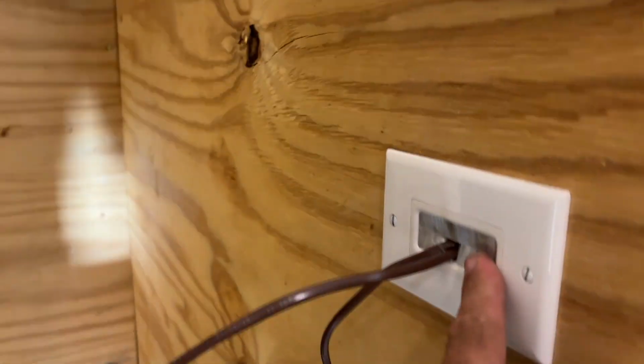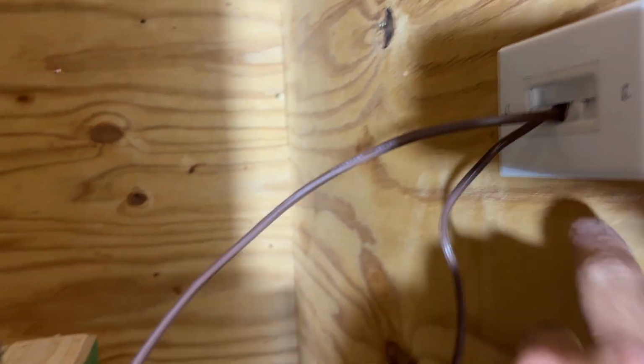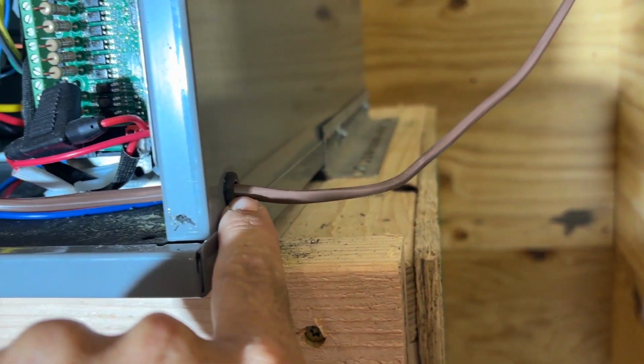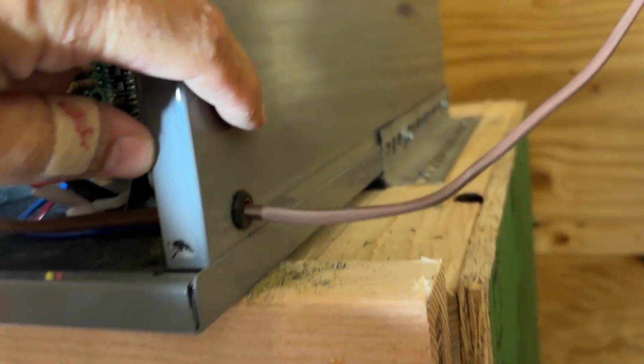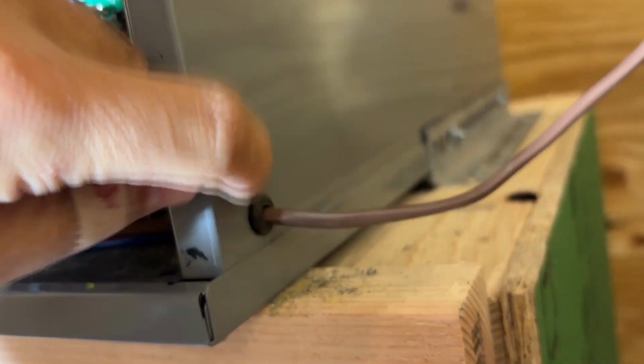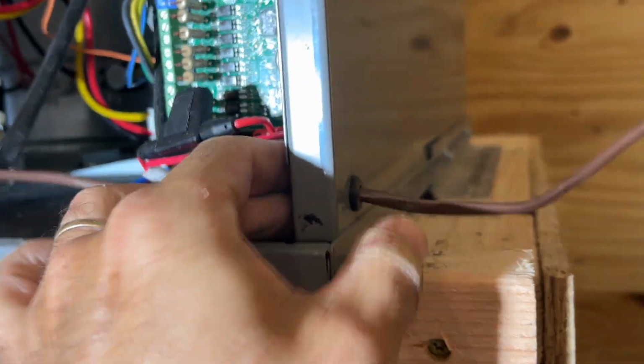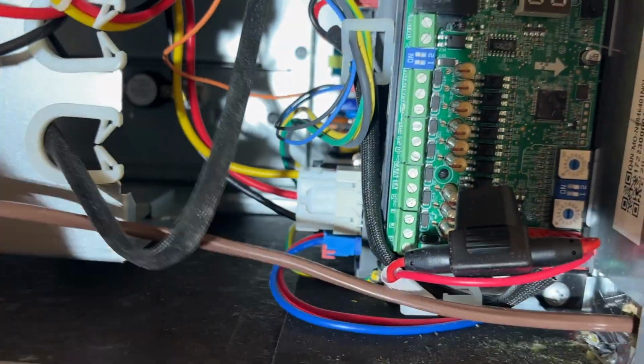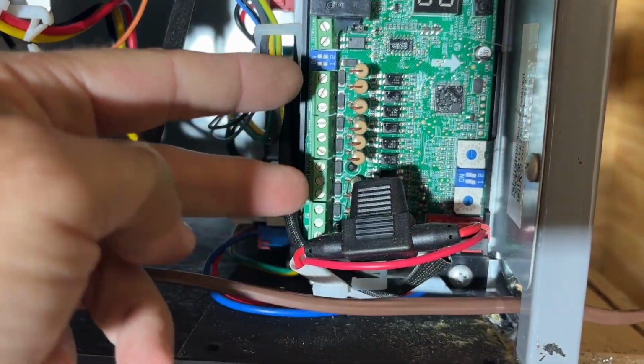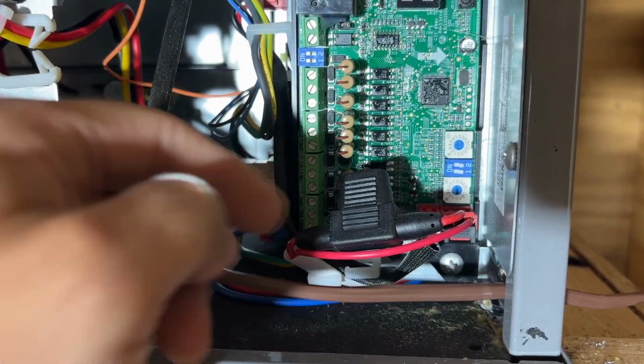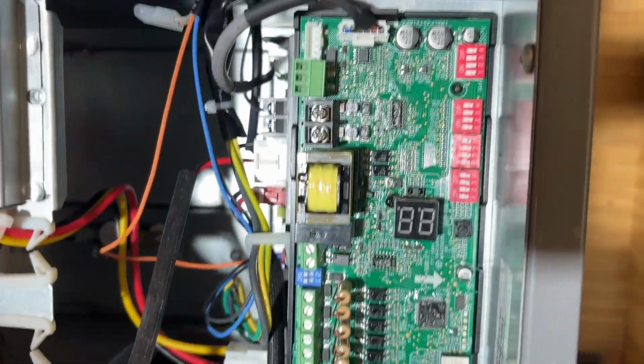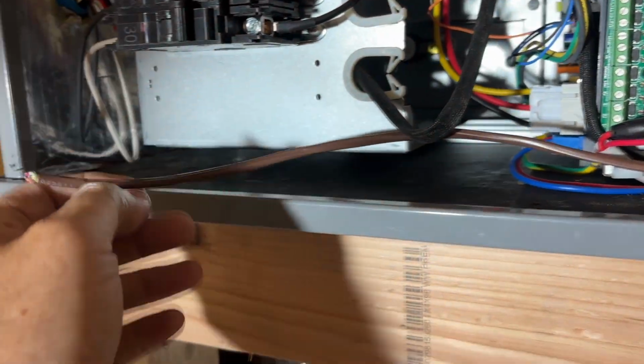So there you go, thermostat wire coming out of the pass-through down into the air handler. I put a little wire grommet on there for the hole so we don't get any chafing, and that's going to work out good because we can bring these right up and connect them into our circuit board there, and we should be in good shape. So let's get those going.